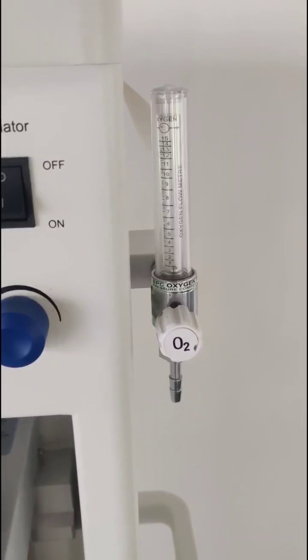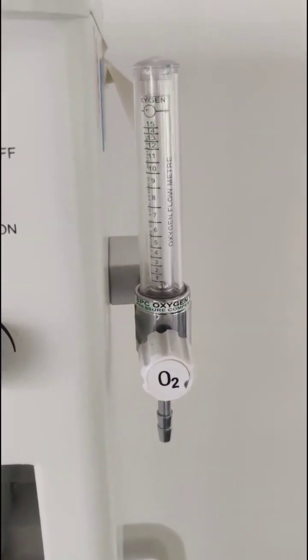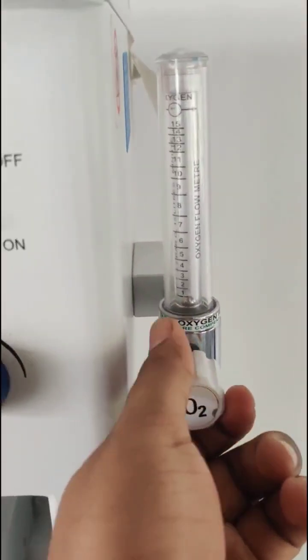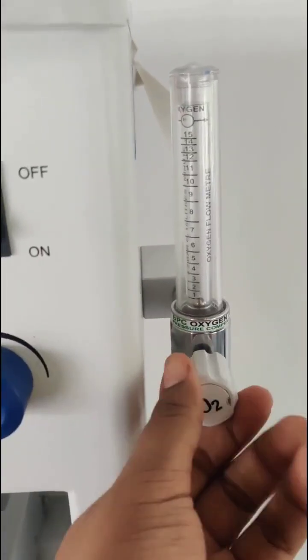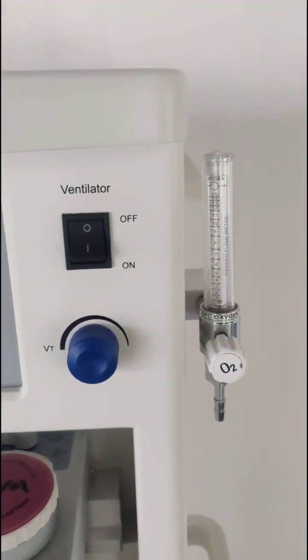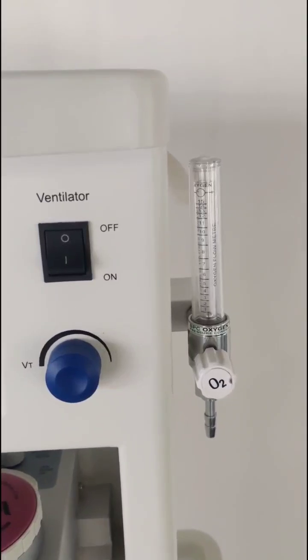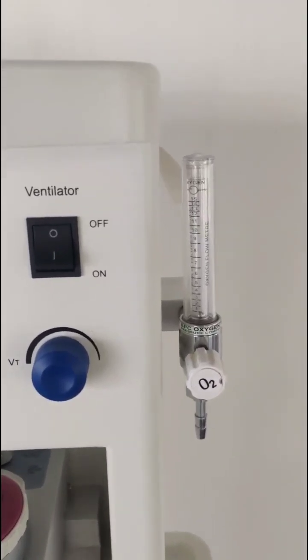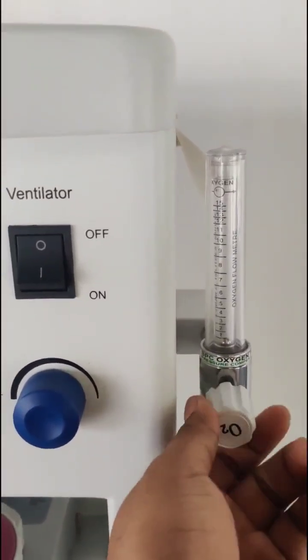On the right side of the machine, we are giving the auxiliary flow meters. Here you can set the flow of oxygen which can be given to the patient. The fresh oxygen can be given to the patient with the help of a venti mask. Even if the machine is turned off, this will be activated and the oxygen flow will be given to the patient.